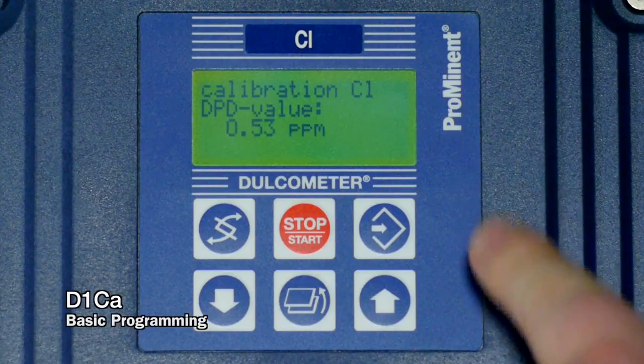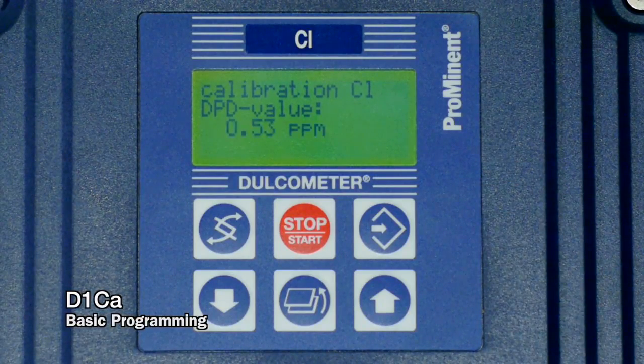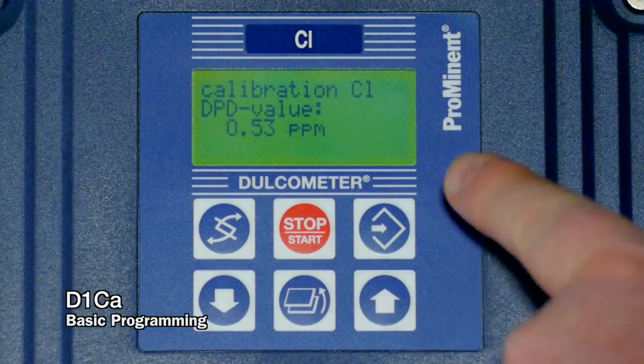The next thing is, it's very important that once we enter to this point where this value starts to flash, we should take our grab sample from our sample line, because this value is actually representing what's in the sample at that point in time. To find out what that value is, we're either going to have to do a DPD type test or a titration, which can take several minutes, and now that number will not represent what we're doing with our grab sample any longer.